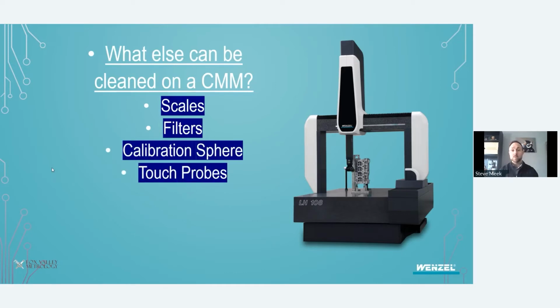And we'll start by talking through some of the scales. These require a little bit more attention to detail because they can be delicate if they're not cleaned correctly, and they are relatively expensive to replace. So we'll start off with a few common misconceptions we see. We'll see a lot of customers blasting the scales with the shop air, the compressed air, to remove some of the dust or debris that might collect on there over time. We see it happening a decent amount, and it will eventually cause serious damage to not only the scale, but the encoder and the reader head as well. And these are not cheap, and they require service visits to replace.